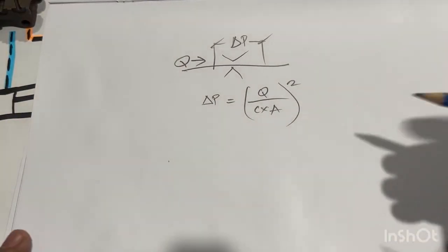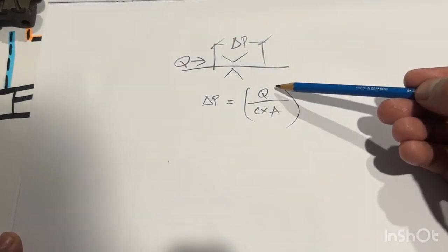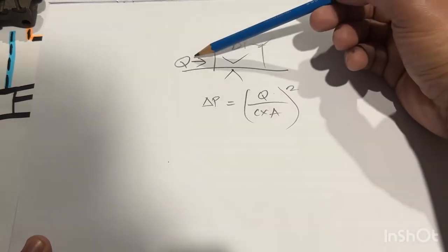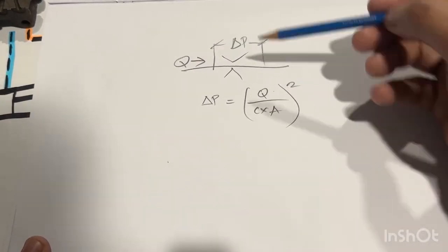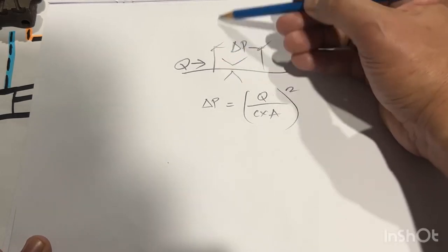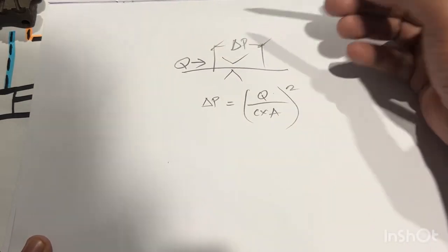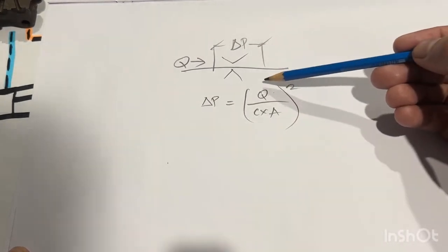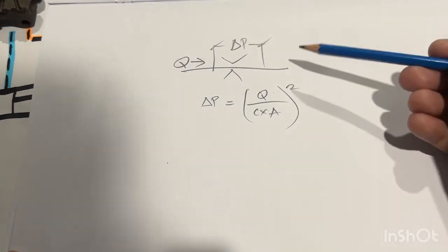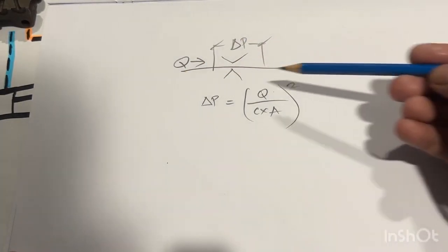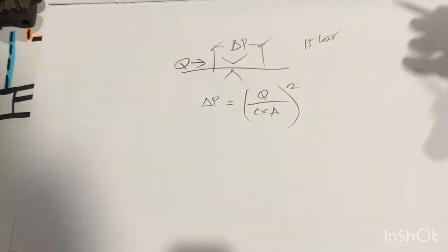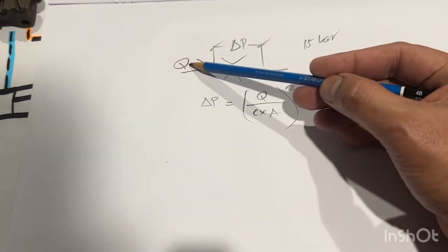Remember, in condition 1 we are at max stroke. When the operator decides to open the throttle valve only 50%, you have a massive flow at max stroke, so the pressure upstream will rise. The delta P is now higher than the spring setting on the flow regulator spool spring. Once that happens, the spool shifts to the left and de-strokes the pump to maintain that 15 bar delta P. To decrease the delta P, you must decrease the flow rate. That's what the pump is doing now.